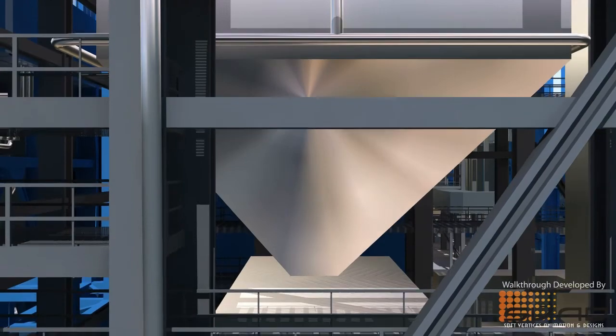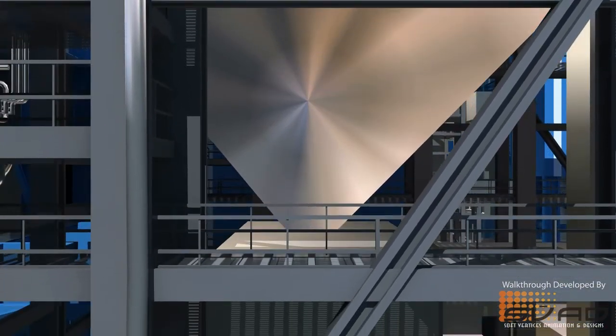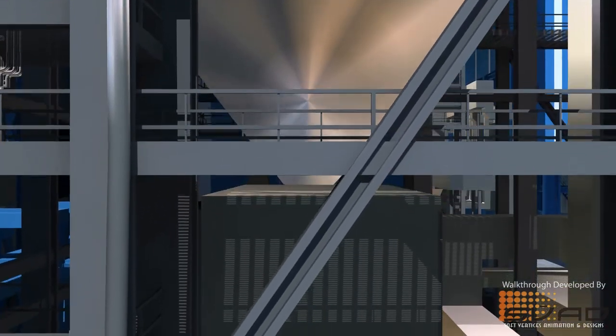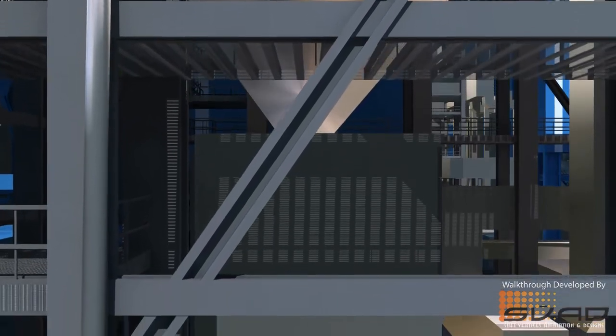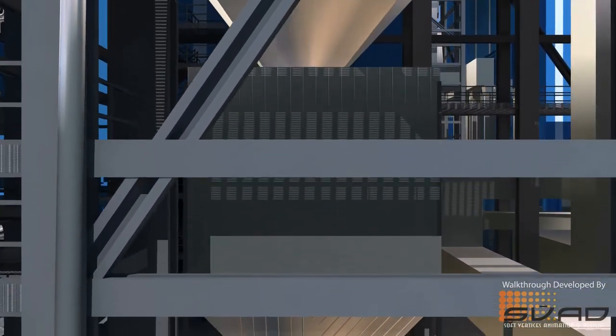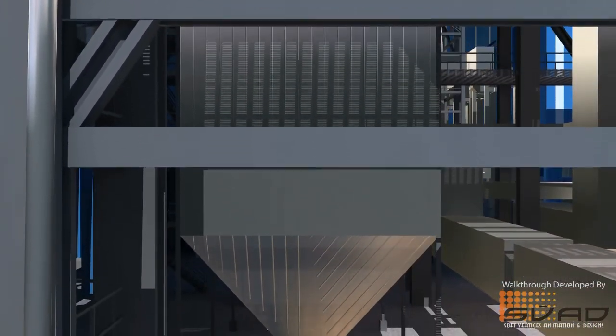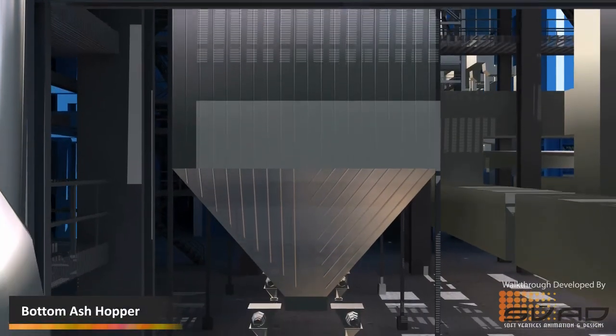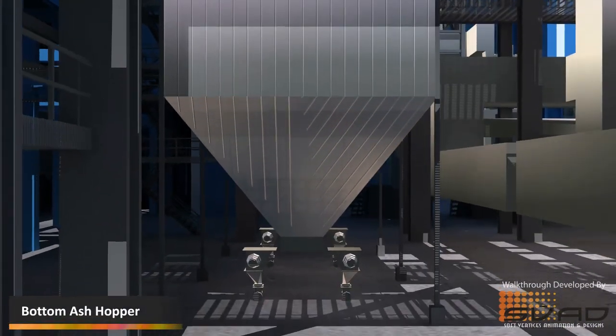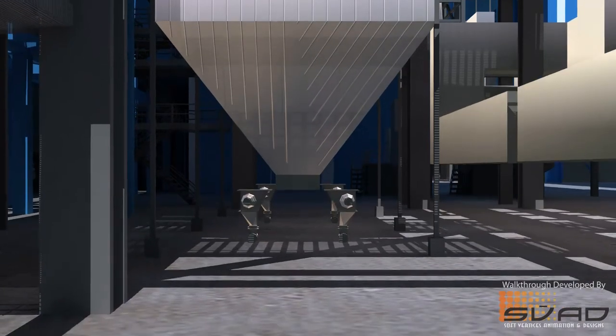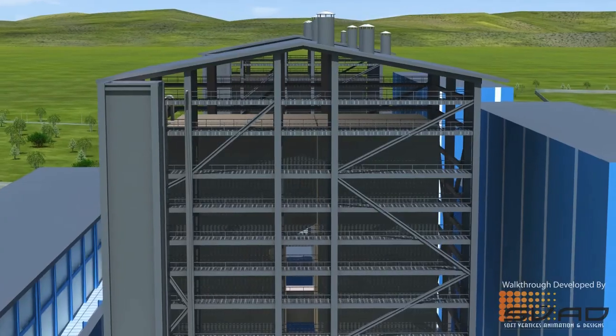Bottom ash hopper is located at the bottom of the furnace for the collection of bottom ash. BA hopper is always filled with water to quench the ash and clinkers falling from the furnace. Falling clinkers and ash are crushed by the clinker grinder and conveyed to the storage site.